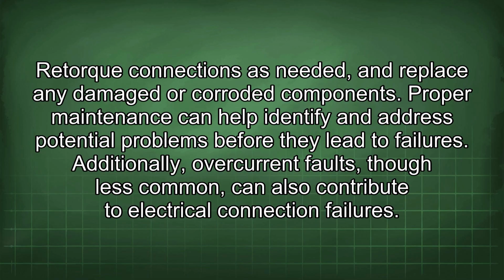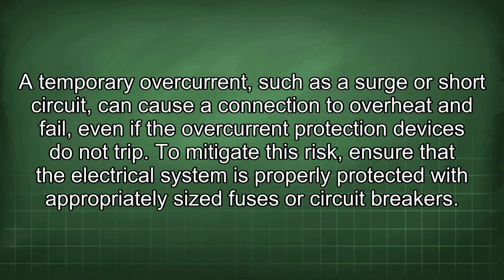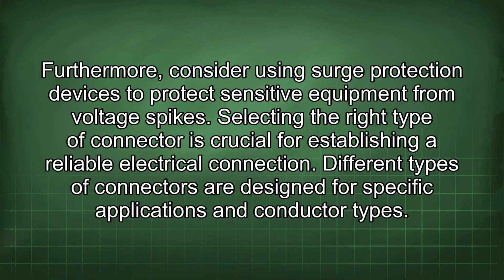Additionally, overcurrent faults, though less common, can also contribute to electrical connection failures. A temporary overcurrent, such as a surge or short circuit, can cause a connection to overheat and fail even if the overcurrent protection devices do not trip. To mitigate this risk, ensure that the electrical system is properly protected with appropriately sized fuses or circuit breakers. Furthermore, consider using surge protection devices to protect sensitive equipment from voltage spikes.